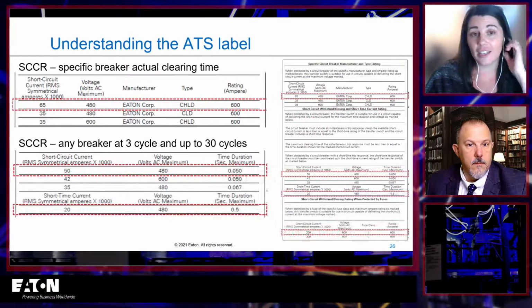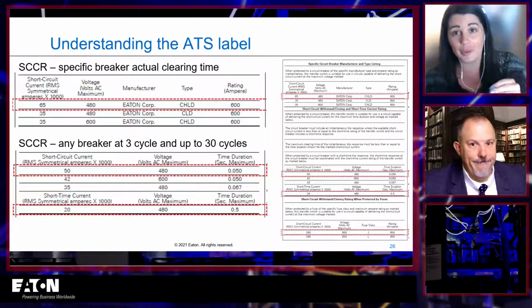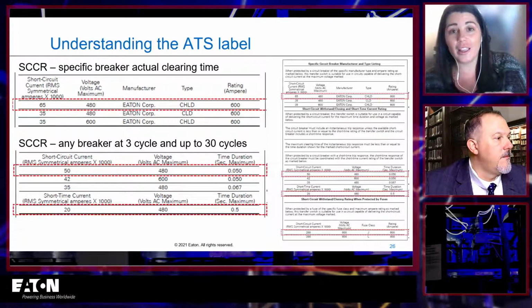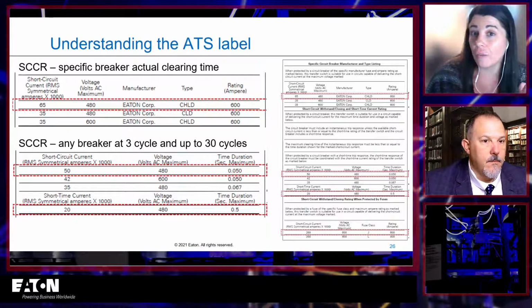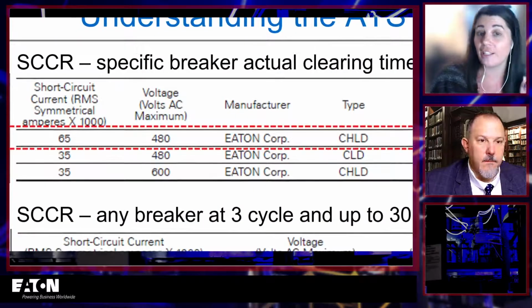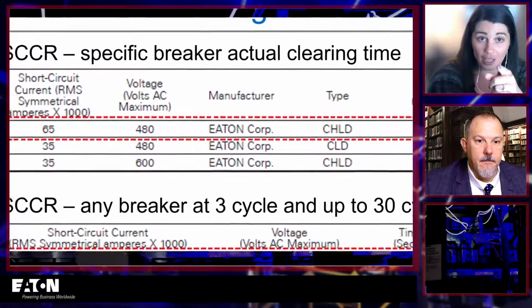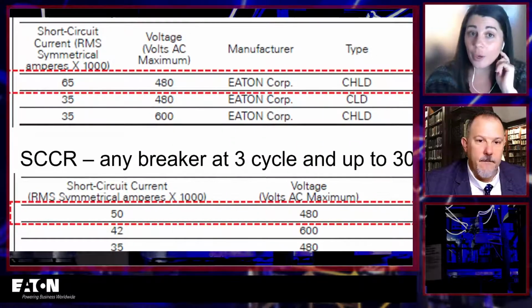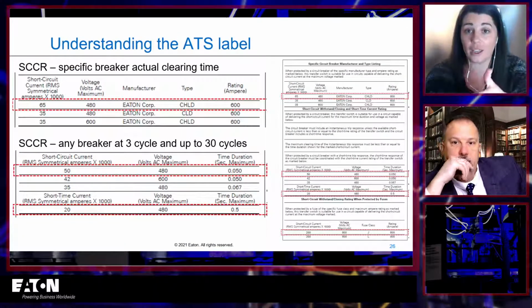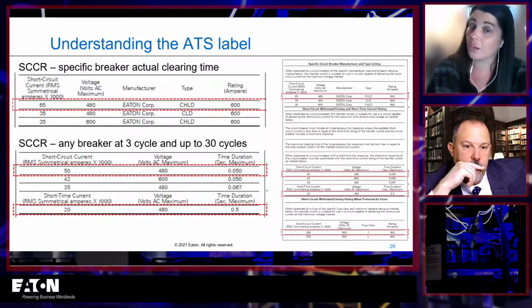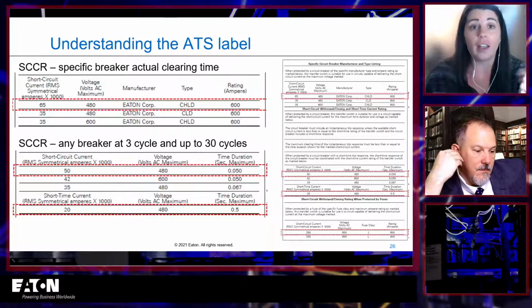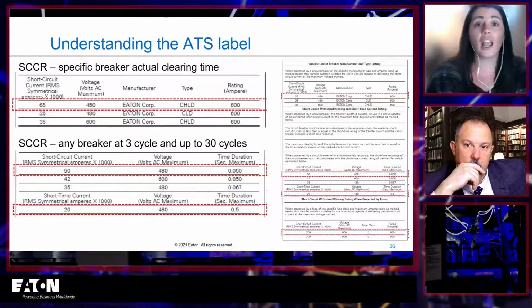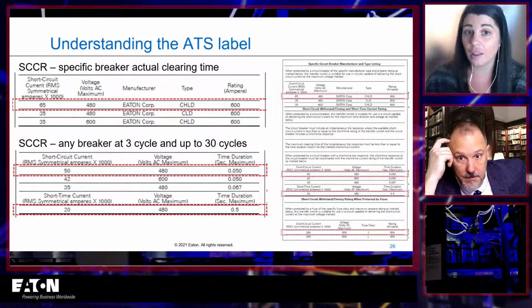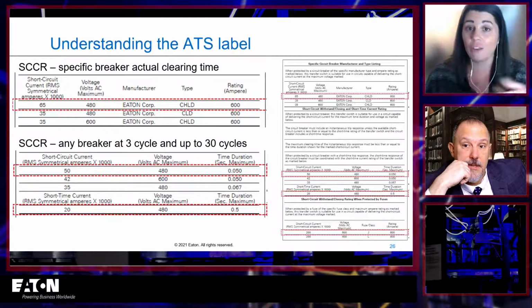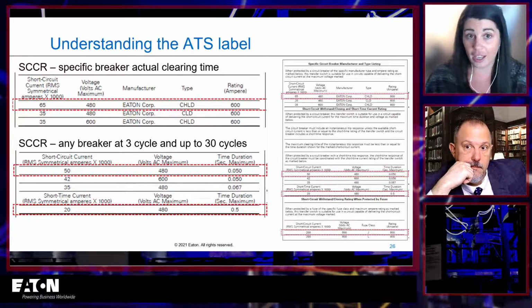If you go to the next slide, they give you a giant label that has about 9 different possible short circuit current ratings on it, depending on what you put upstream. So there's an SCCR based on having a specific breaker. So this is an Eaton transfer switch, and they say, okay, if you have these specific Eaton breakers in front of it, it'll have this SCCR. And it'll also have different ones at different voltages. And then if you use anybody's breaker, and it opens in this amount of time, in 3 cycles versus 30 cycles or anything in between, it might have this different SCCR.